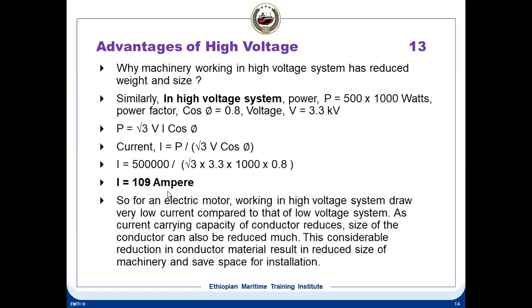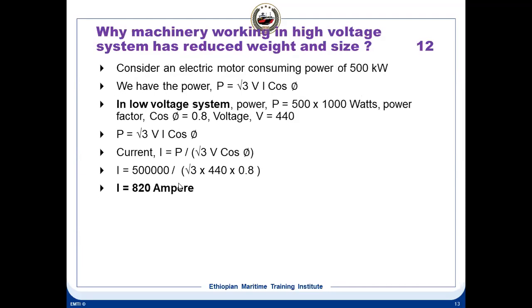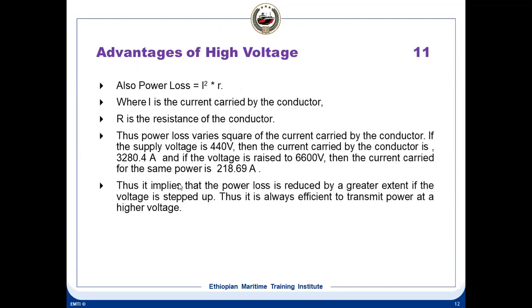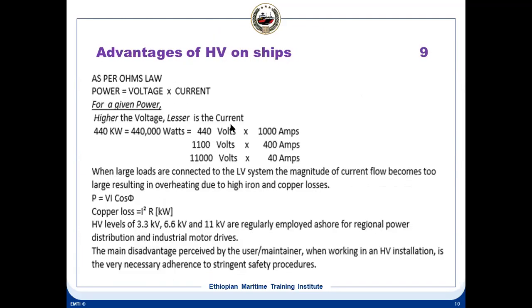So from these two examples, it's very clear that when you step up the voltage, the current is reduced. So the rating of your cables, your switchgear, everything comes down. Cost wise, rating wise, space wise, everything will be reduced. This is one of the great advantages of using high voltage. What we have discussed is only this: for a given power, higher voltage means lesser current. If you start increasing the voltage, the current rating will come down.